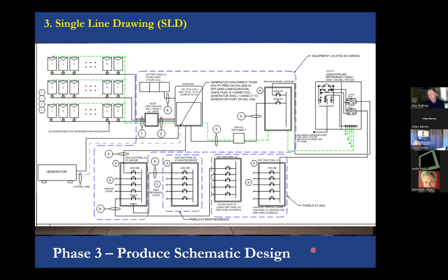Here's a 400 amp main service connected to the utility. What's going on here is what we think is the most practical system, where the owner said they only need partial loads backed up. 200 amps is a lot of juice to back up, so what we've done is broken it up. 200 amps goes to our hybrid solar energy hub, which uses the PV, batteries, and maybe a generator to back up our critical loads panel.